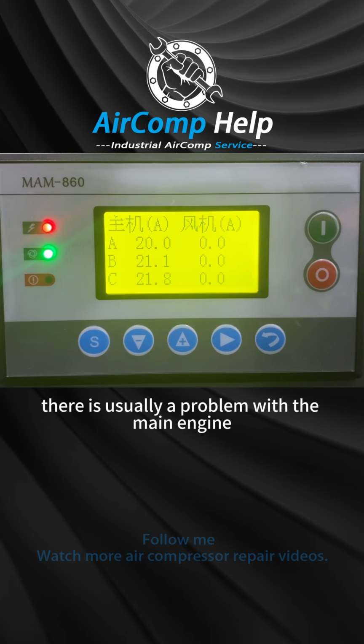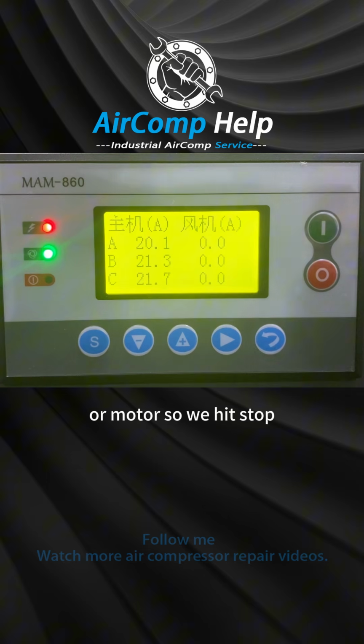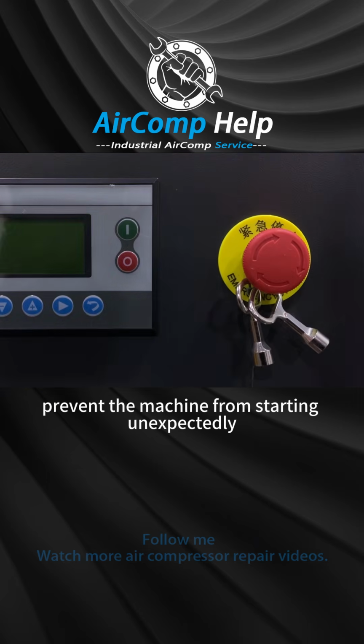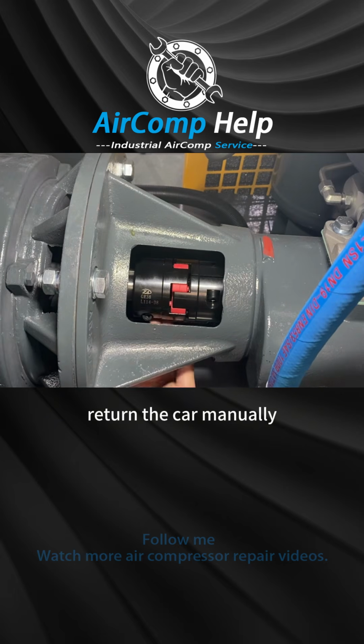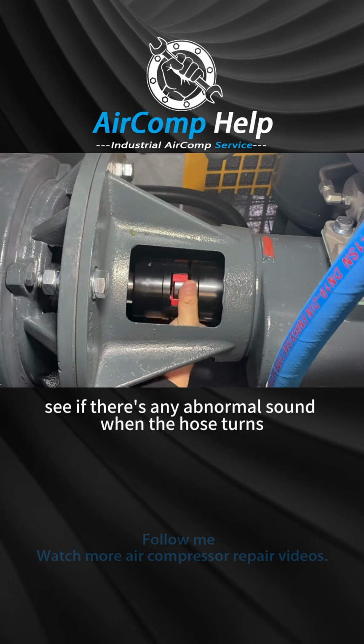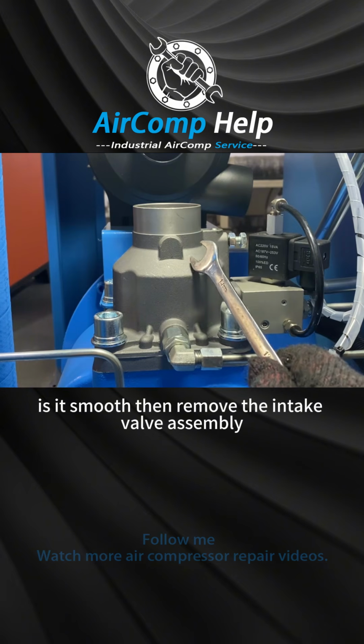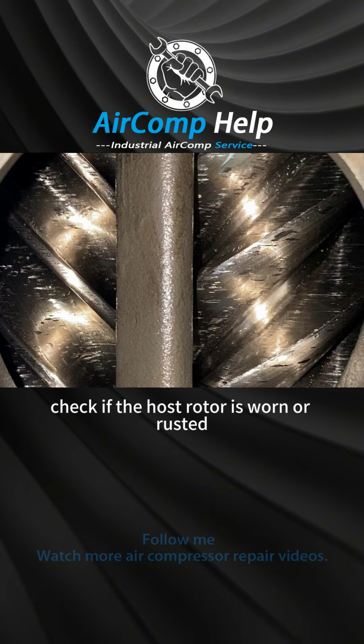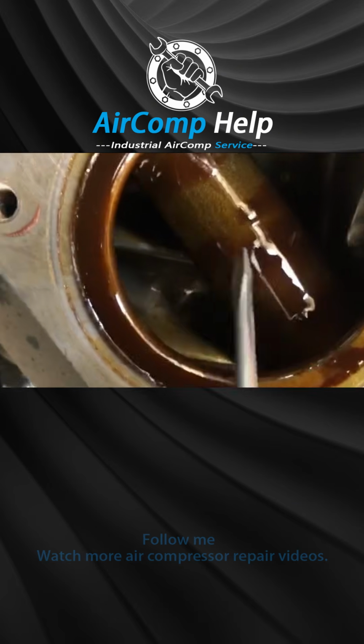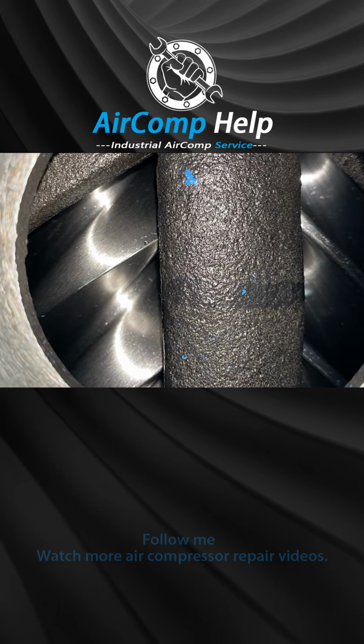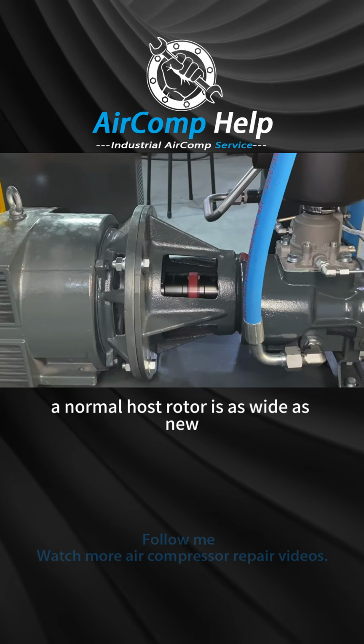In this case, there is usually a problem with the main engine or motor, so we hit stop to prevent the machine from starting unexpectedly. Turn the machine manually, and see if there is any abnormal sound when the host turns. Is it smooth? Then remove the intake valve assembly. Check if the host rotor is worn or rusted, and whether the oil is gelled. A normal host rotor is as white as new.